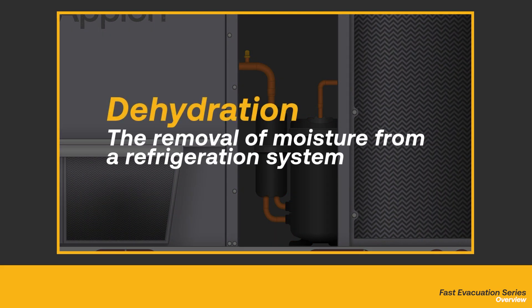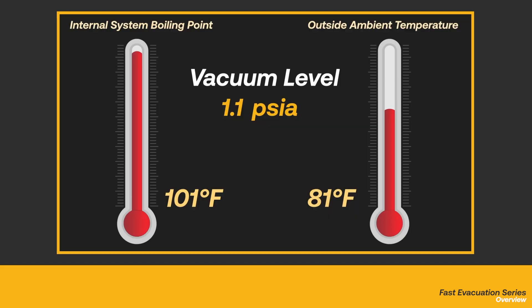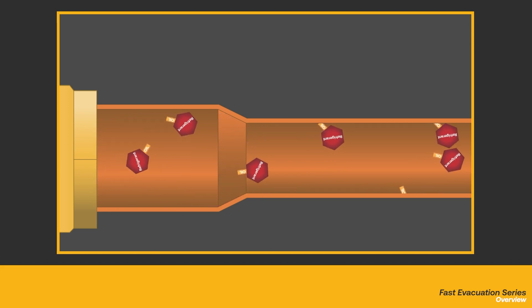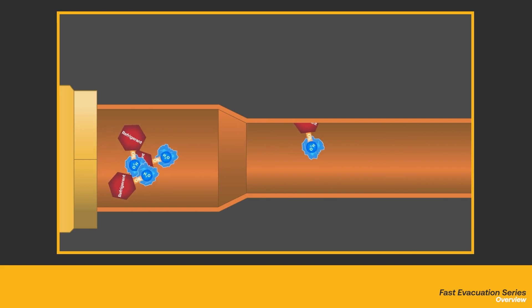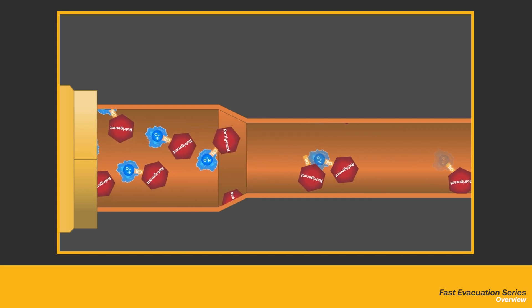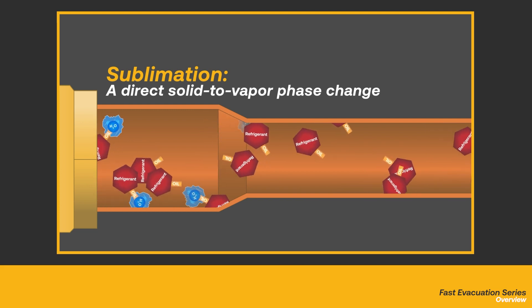Dehydration is the removal of moisture from a refrigeration system. This process is the fundamental reason why pulling a system into a vacuum is so necessary. As we pull a deeper and deeper vacuum, what we're actually doing is lowering the system's internal pressure, thus lowering the boiling point of water. The goal of a deep vacuum is to pull it deep enough that the boiling point inside the system is the same or lower than the ambient temperature outside of the system. The ambient temperature will then be hot enough to evaporate any liquid moisture, which will be evacuated through the pump. If there is a high level of moisture in the system, it will freeze before it can be removed as vapor. Fortunately, ice will sublimate, which means it can change state from a solid directly to a vapor. Increasing the vacuum in the system will further reduce the boiling point, aiding in this process.